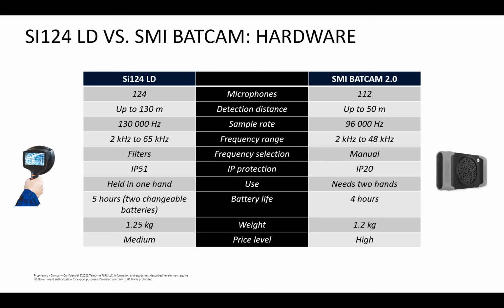Sound over 65,000 hertz behaves in a very random way - it opens and spreads dramatically. So you'd need to place the camera very close, maybe 5-10 centimeters from the leak source or partial discharge source, for the camera to detect that sound. In partial discharge, that's impossible because you'd basically die getting so close to the source - there would be an accident.